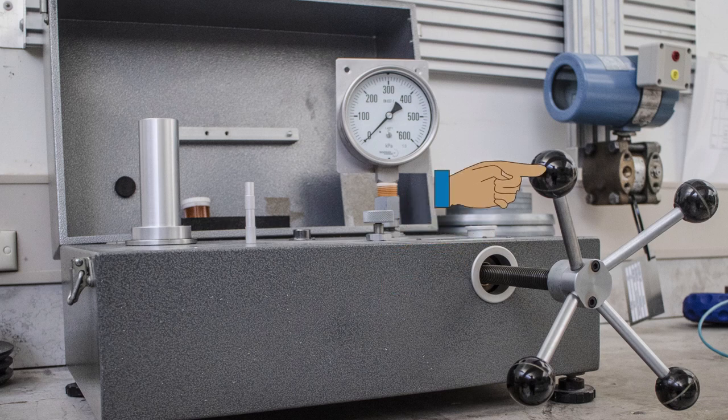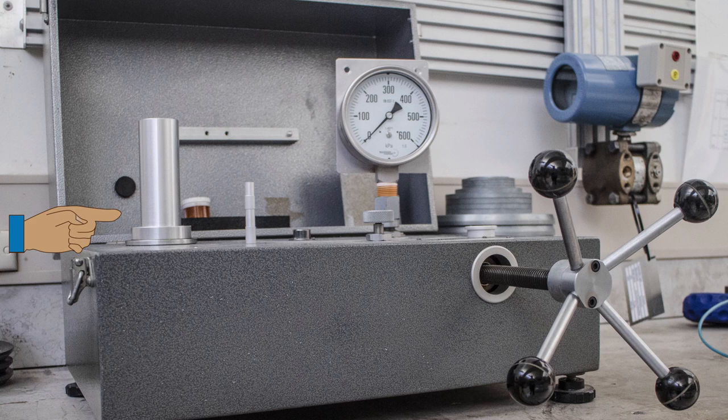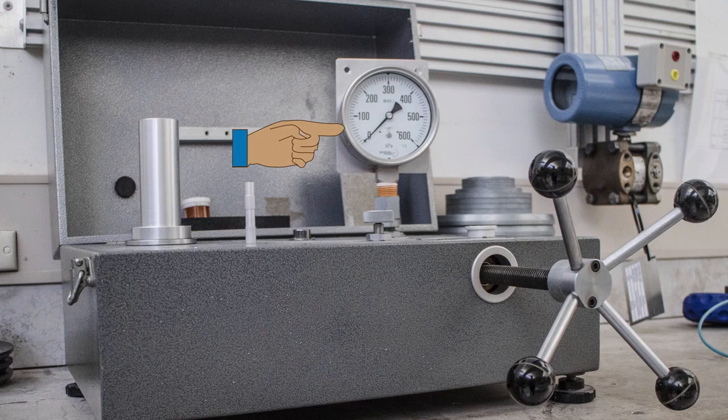The pressure is increased by turning the handle. When the pressure from the pump equals the pressure caused by the weight on the piston, the piston will pop up. The reading on the test instrument can then be checked and recorded.